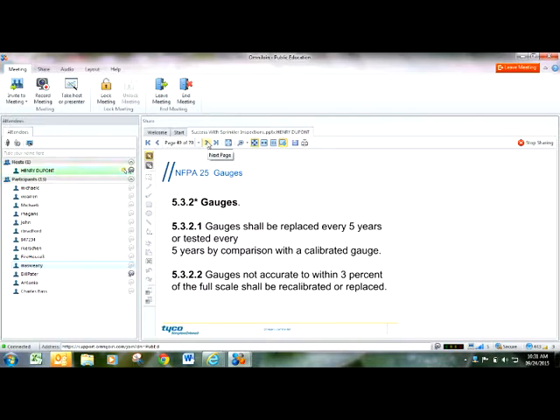Sprinkler gauges shall be replaced or tested every 5 years. We don't get a lot of requests to have gauges calibrated. It costs about 10 times more to calibrate a sprinkler gauge than to just replace it. I know that we carry a stock of gauges on our trucks, and if we notice that gauges are over 5 years old, we can sell the customer a sprinkler gauge right there on the spot. Every sprinkler gauge has a date written on the face of it too, so there's not a lot of guesswork. If you don't see a date on the gauge itself, you might question whether that's a UL/FM approved device.